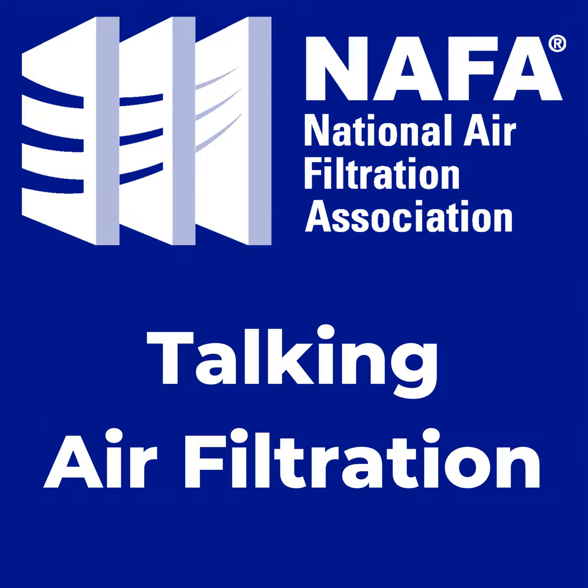Other challenges we've seen with nanofibers is inconsistency in what we receive from the process. Because of the electrospinning process, if you put just a very fine layer of nanofibers on there, it can sometimes get damaged or pulled off during, I don't know if it's the rolling or shipping or manufacturing of pleating the filters. But depending on how you're using the nanofibers, you can have difficulties with these.